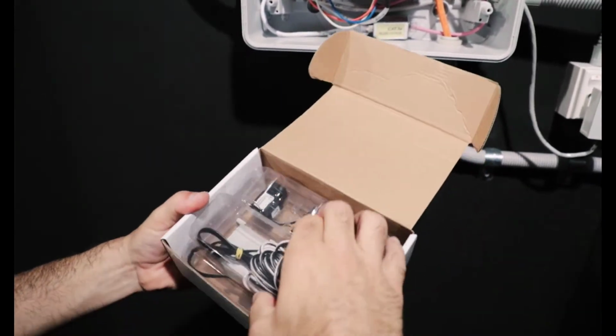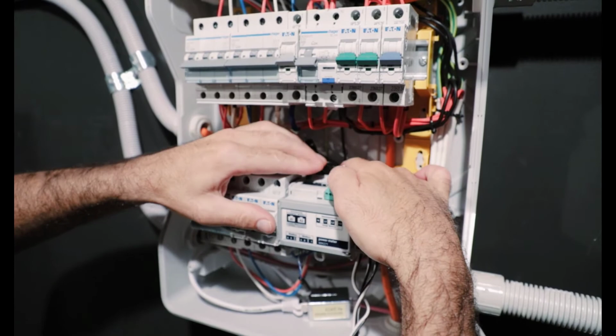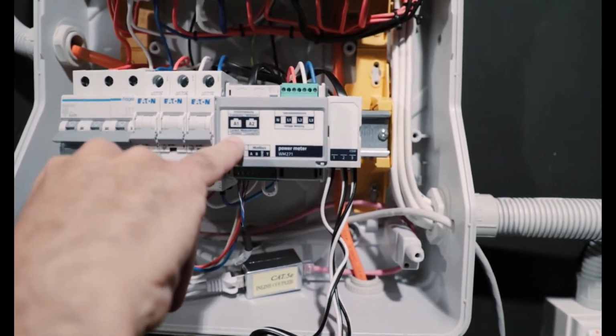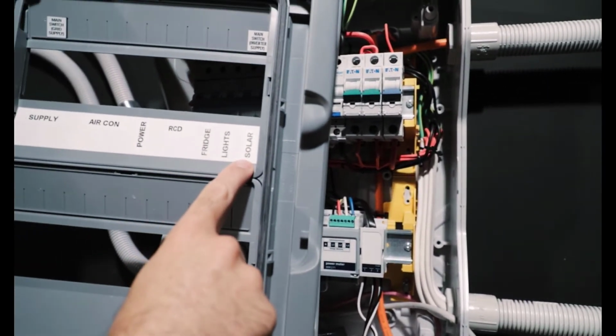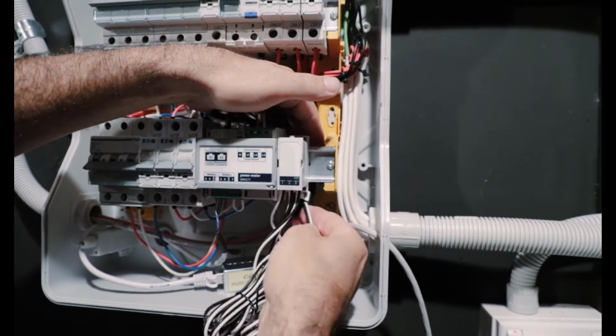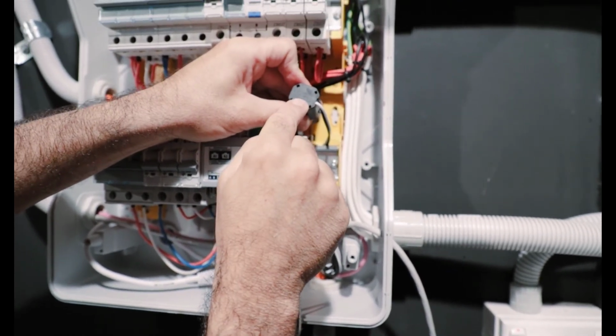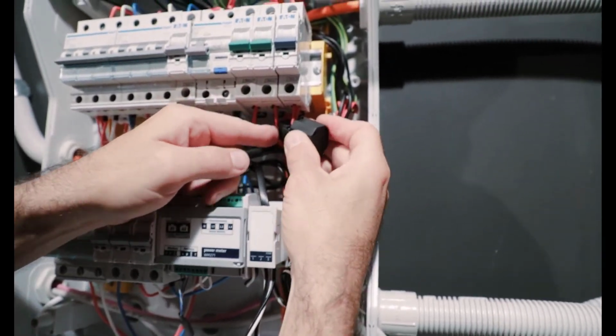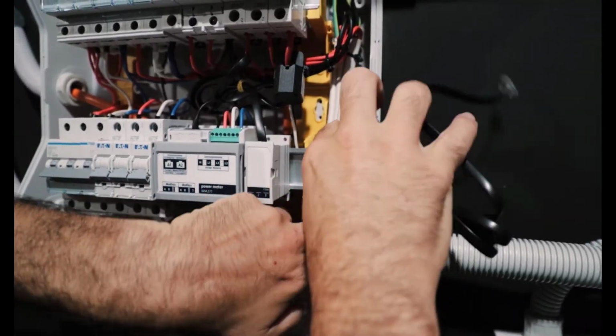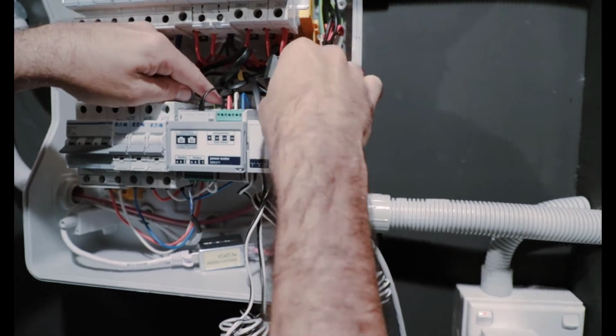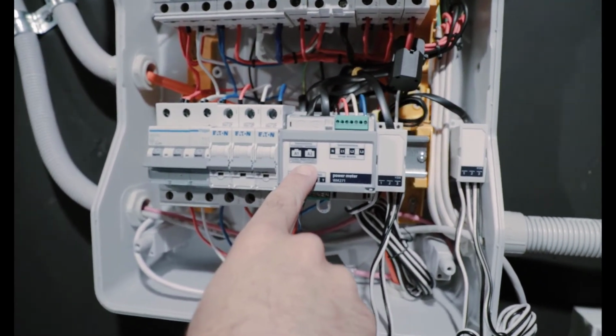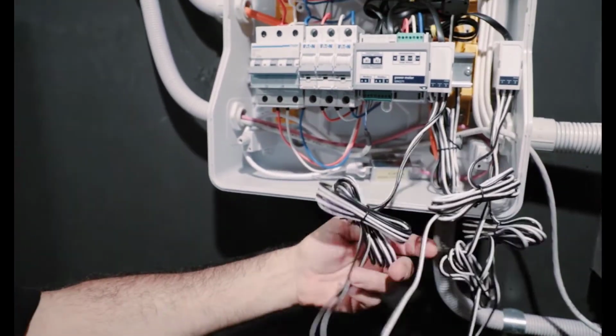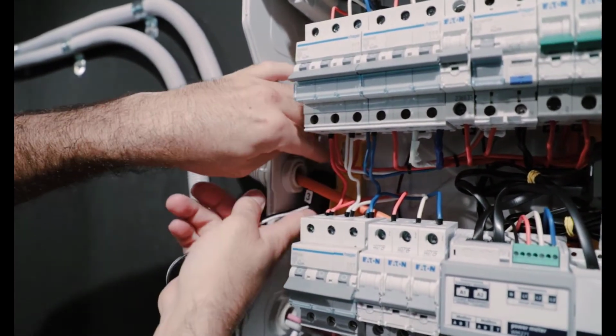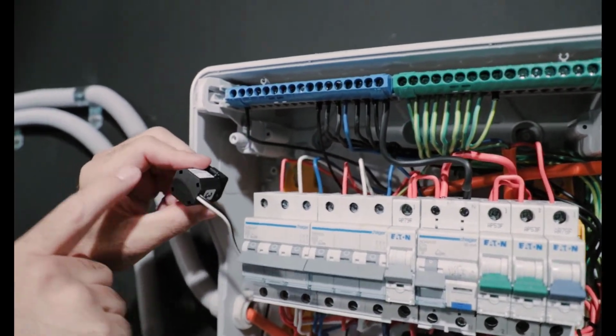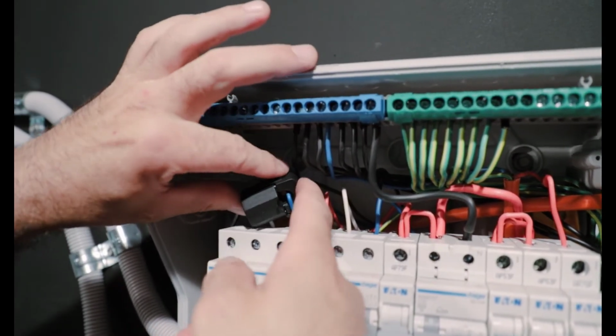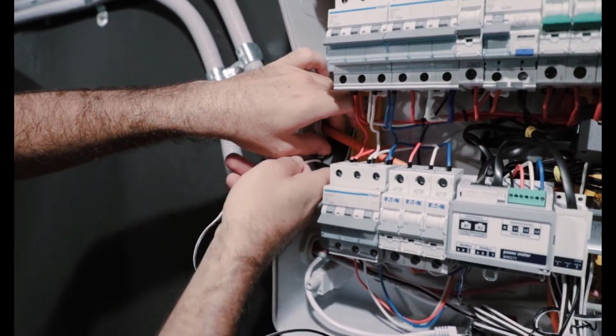Now we take our CT sets once more. First CT set we put into A1 because we're going to be measuring the generation for the existing solar, which is this MCB here. Again, ensuring you get the CT the right way around. Look at the arrow in the direction of travel, if you like, of the power, and that just simply goes onto the AC out of the MCB. Next one, we're then going to take our CT set for all of the consumption measurements. Now, given this is a little bit more involved in this switchboard, what I'm doing here is wiring the CTs in reverse, going 3, 2, 1, just because it's a bit simpler more than anything, nothing special about it.